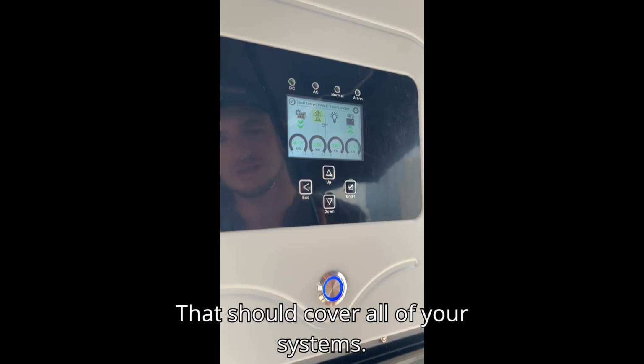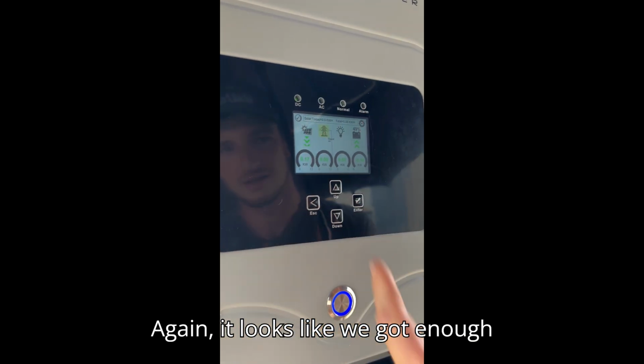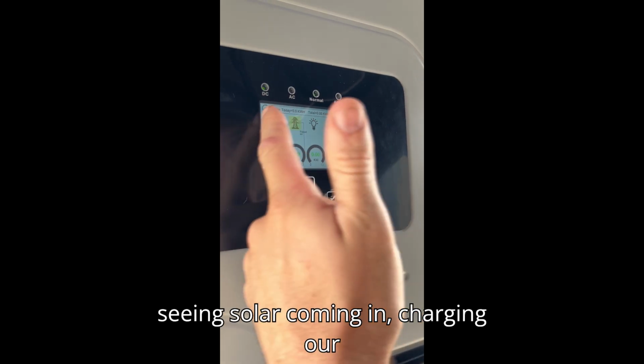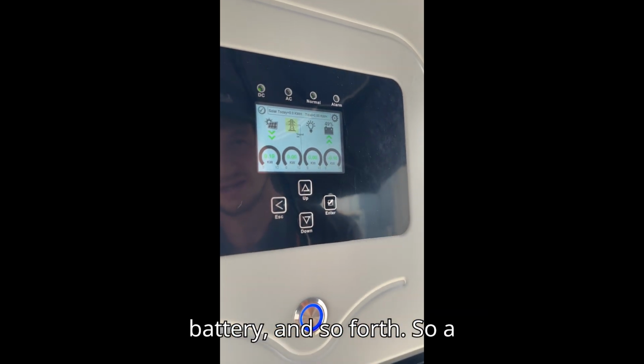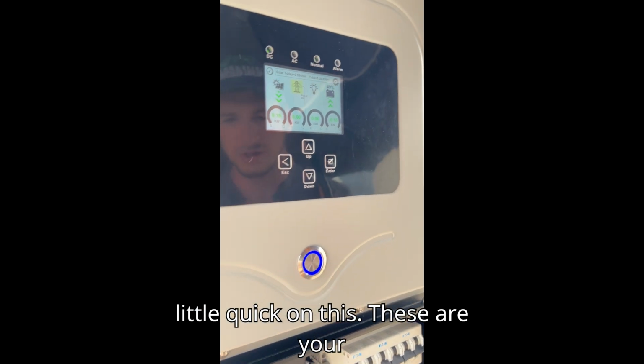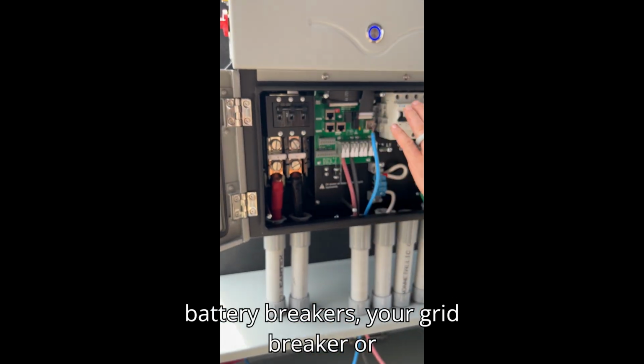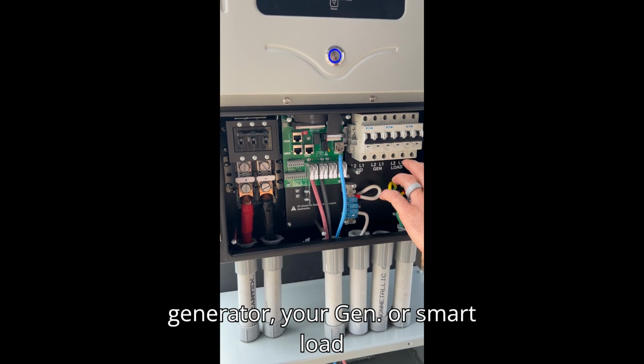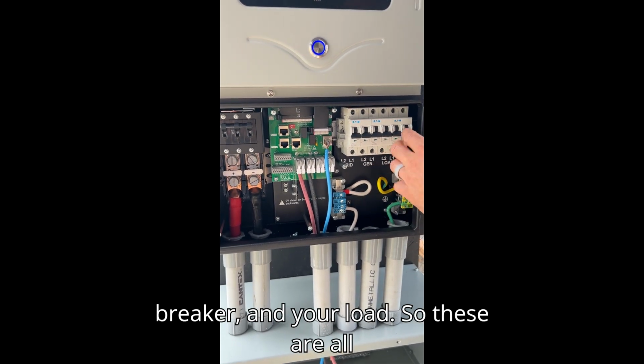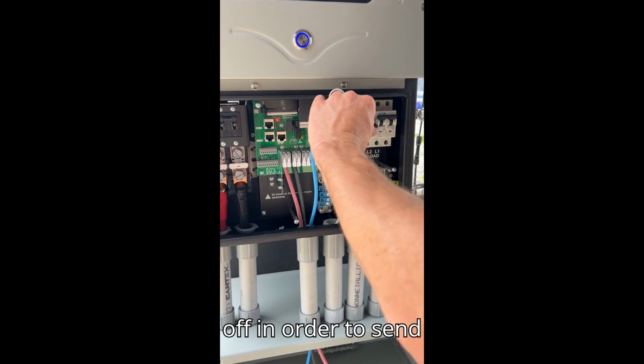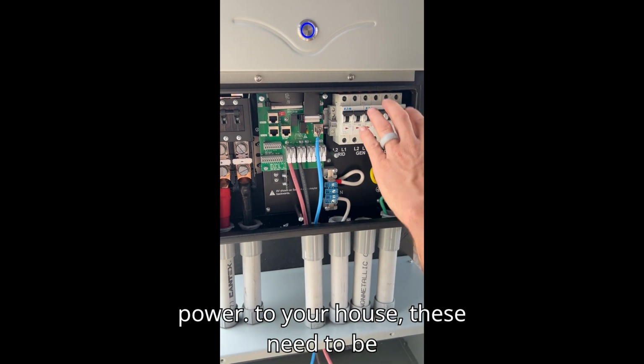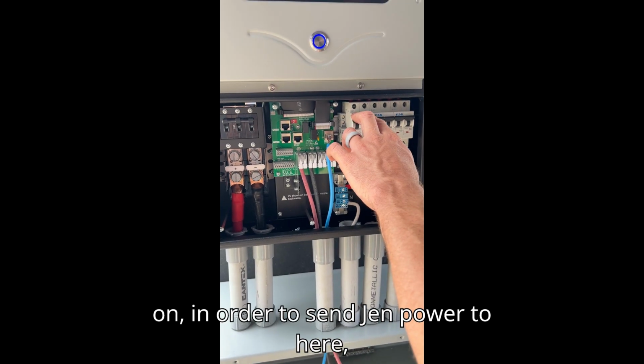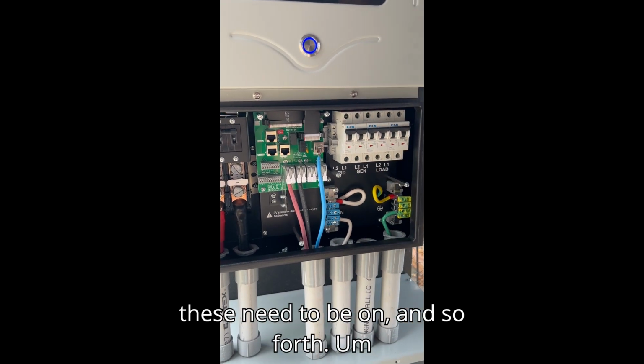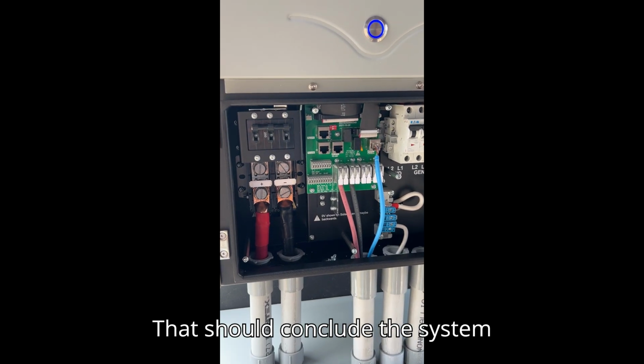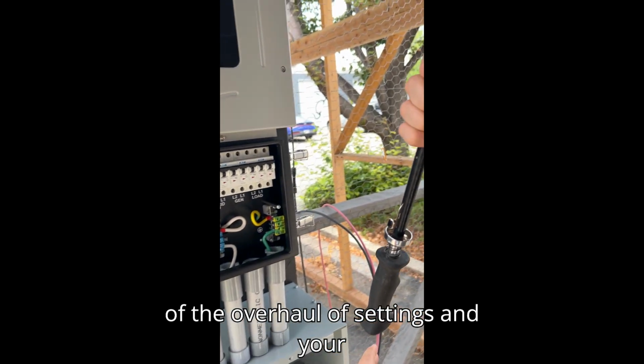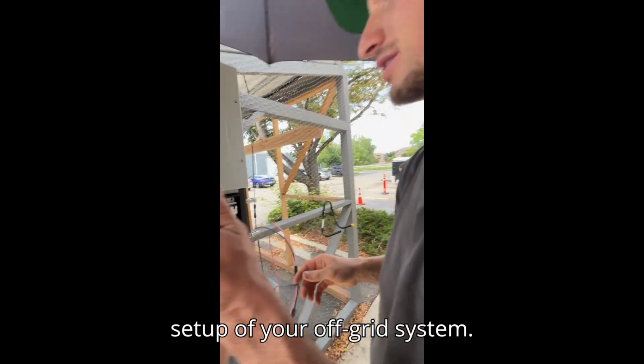That should cover all of your systems. Again, it looks like we got enough voltage to bring in solar, so now you are seeing solar coming in, charging our battery, and so forth. So a little quick on this. These are your battery breakers, your grid breaker or generator, your gen or smart load breaker, and your load. These are all off. In order to send power to your house, these need to be on. In order to send gen power here, these need to be on, and so forth. So that should conclude the overhaul of settings and the setup of your off-grid system.